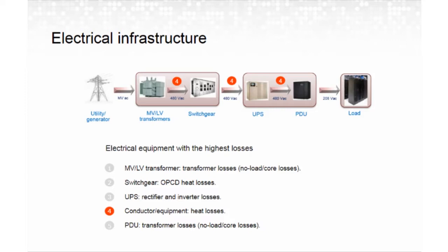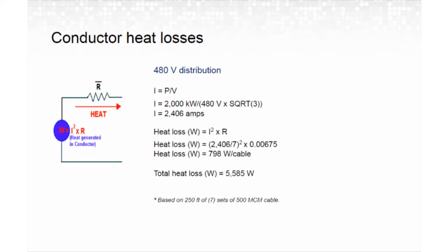The next piece we want to look at is the conductor losses. So basically the conductor is current going through a resistor, so that creates heat. And when you look at the low voltage side, which is a lot of conductors with a lot of current flow, for example, on a 480 side, there's a 2,000 kW load, it's about 2,400 amps. So that results in about an 800 watt per cable heat loss, 798. Because you need a lot of cables to run that type of amperage, you're looking at seven sets of cables. So that's a total of 5,585 watts for that one feeder.